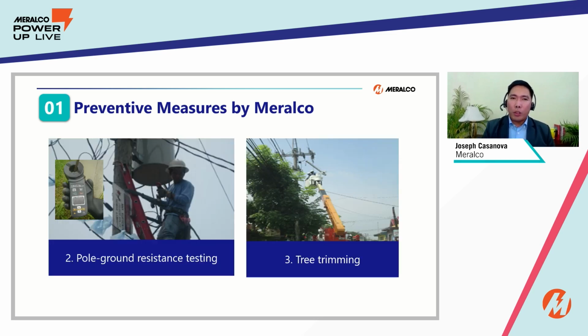Next, we also do test ground resistance of our poles. So this will ensure efficient grounding which protects our lines and facilities, especially during lightnings or thunderstorms. So we ensure that our grounding is within the allowable resistance needed for effective and safe dissipation of induced electrical energy. So technically 10 ohms dapat at most yung mga ground resistance natin.